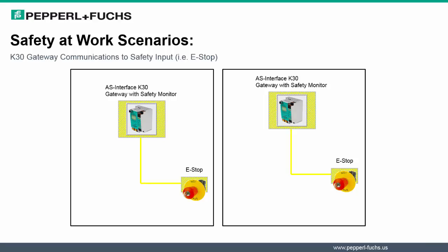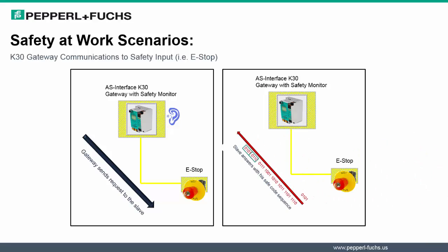Let's proceed to discuss a typical arrangement of a K30 gateway communicating to a safety input. In this scenario, first the gateway sends a request to the safety input or slave. The safety controller, in this case the K30 gateway, listens for a response back from the safety input. The safety input responds with four bits of data, like any other I/O module. But with the safety input, the four bits transmitted from the module to the AS Interface gateway follow specific rules that allow the safety monitor to determine whether the e-stop has been activated.